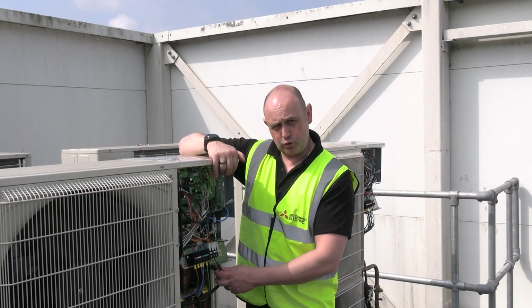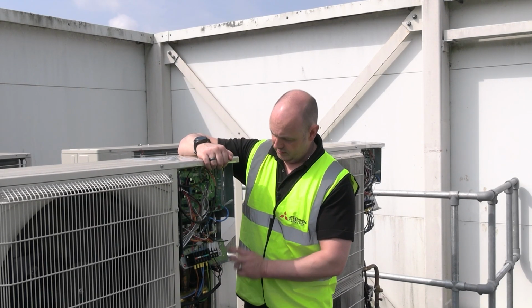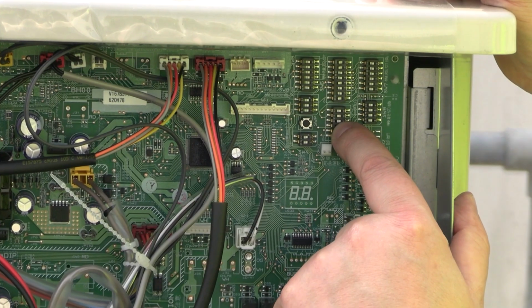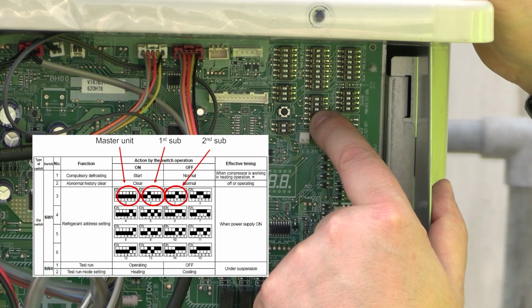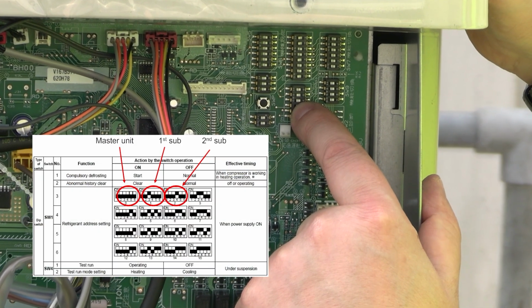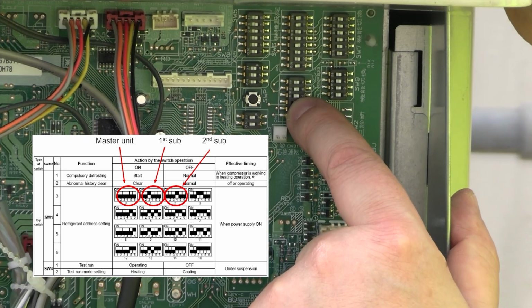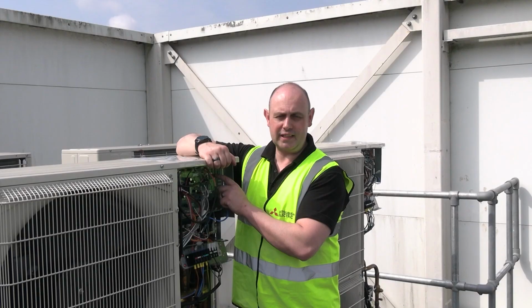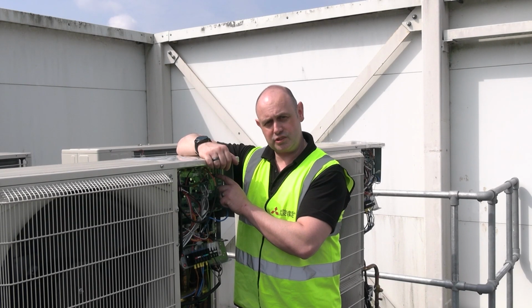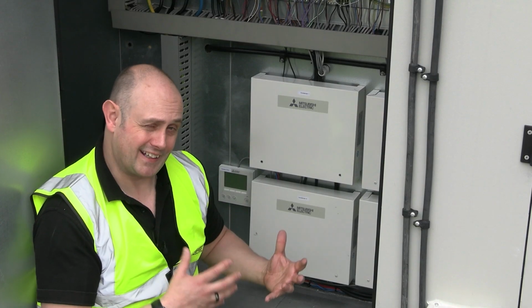The thing we need to do with the outdoor unit is do the addressing side. So on here, SW1, we need to change that to tell it this one here is actually unit 4, because we've got 6 units connected to this air handling unit, and this one's unit 4, just so the actual system knows what's going on and you can actually interrogate it on the control if need be. Inside the air handling unit, we've got the PAC-IFs.